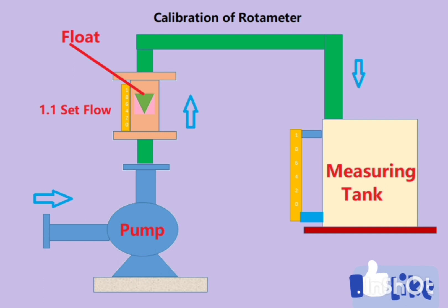Suppose we want to calibrate this rotameter for four liters per hour flow. We start the pump, set the float at the four liter per hour mark, and begin collecting liquid in the measuring tank. After one hour, we stop the pump and check the collected volume. If it is four liters, the rotameter is 100% accurate. If it is higher or lower, the rotameter is showing error. This is a very simple manual calibration setup.